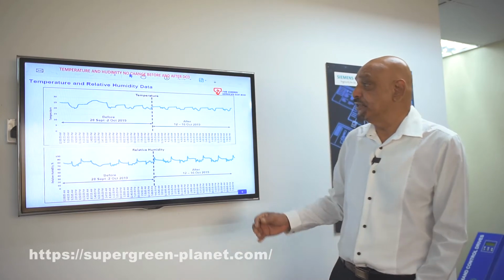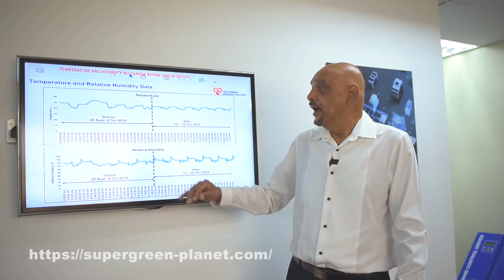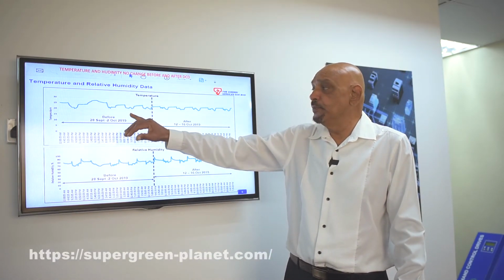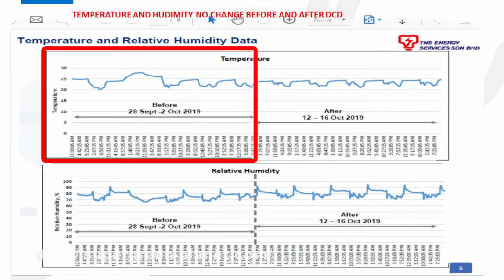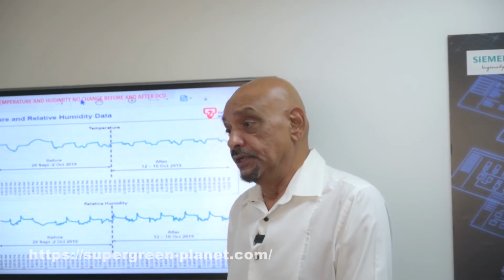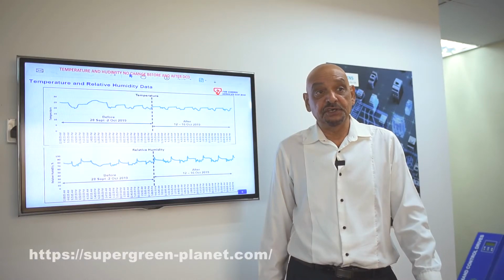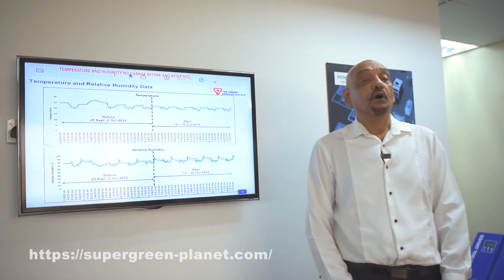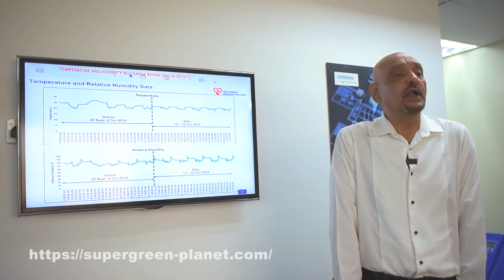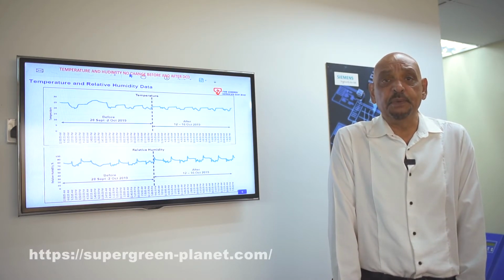What we got was, for example, the relative humidity, and this is the relative humidity before DCD was installed. Now, the way the measurement was done, for example, data loggers or power meters were installed to that particular air handling unit before we even installed the demand control drives, and the temperature meters were placed at strategic locations. The whole exercise was done within a 2 weeks period.